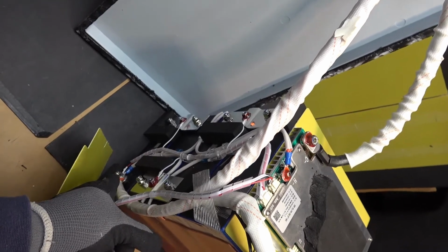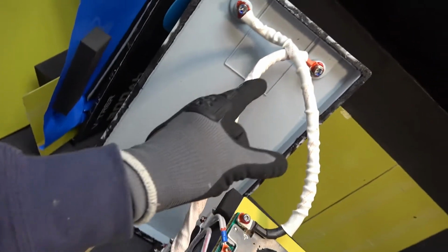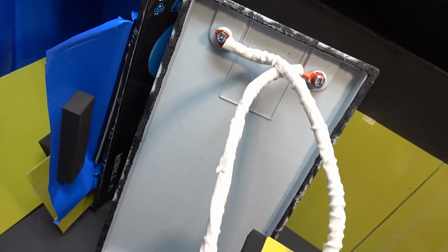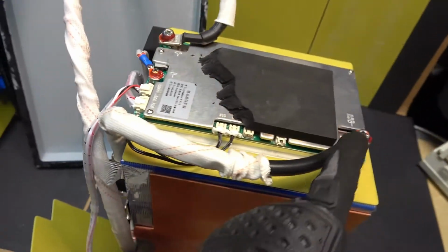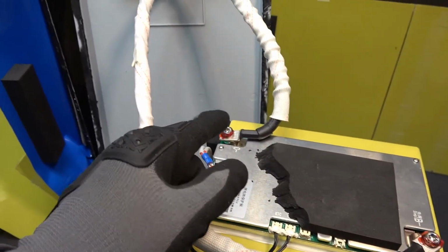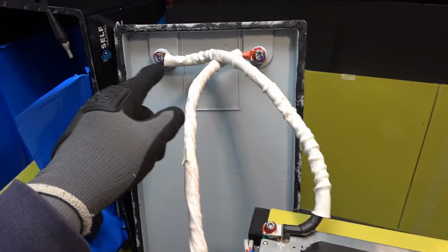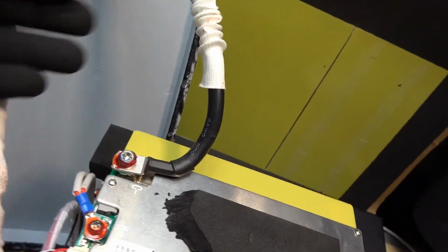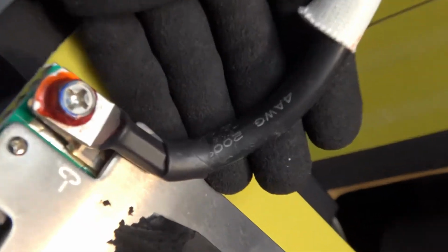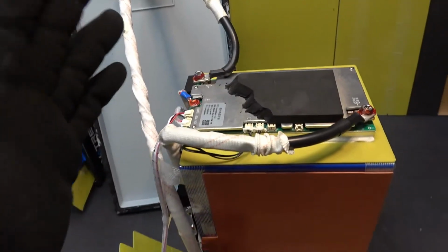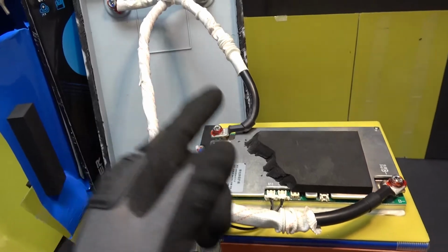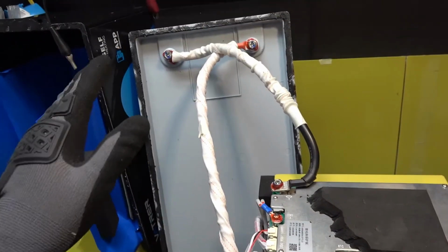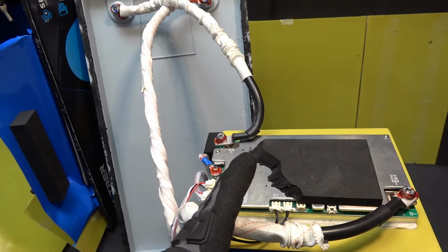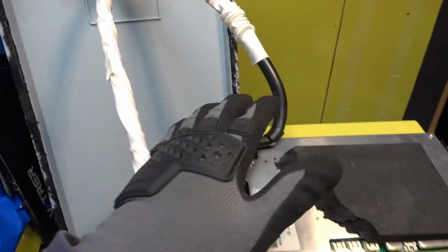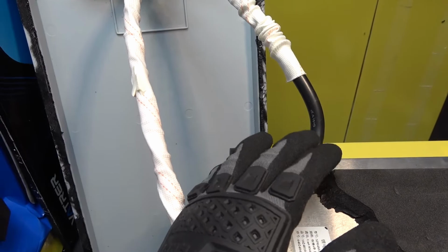The positive terminal from the battery goes straight to the main positive terminal on the top. The negative terminal from the battery goes to the BMS, and then output from the BMS to the main negative terminal on the top. And the wire they use is size 4. Most 100 amp hour batteries use size 6, but because this is 300 amp hour and the BMS is rated at 200 amps, they have to use a bigger size wire.